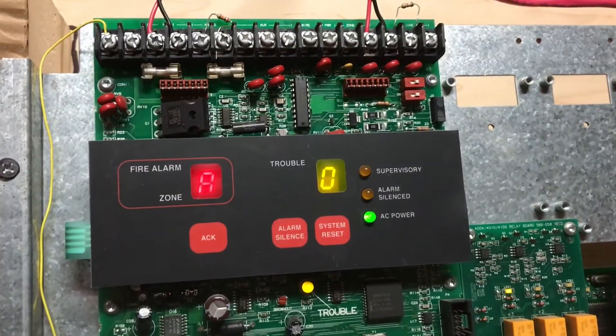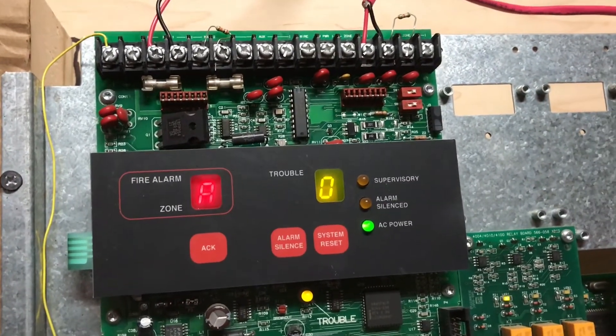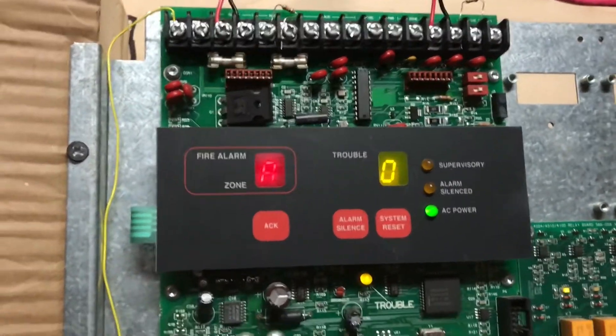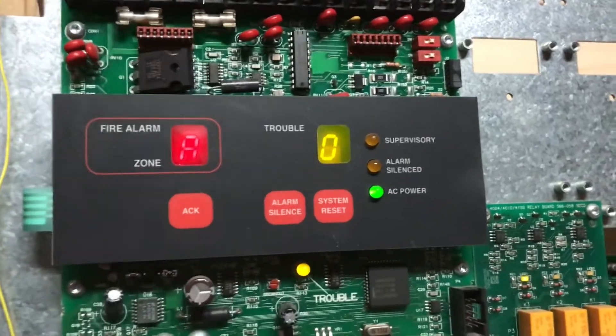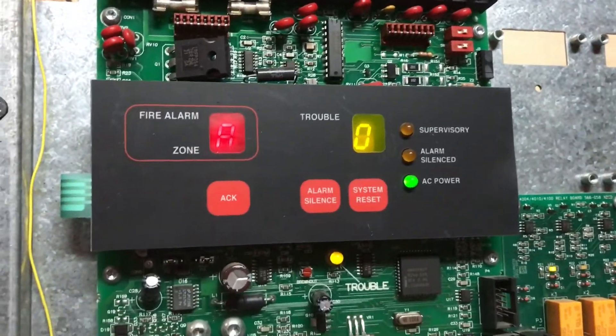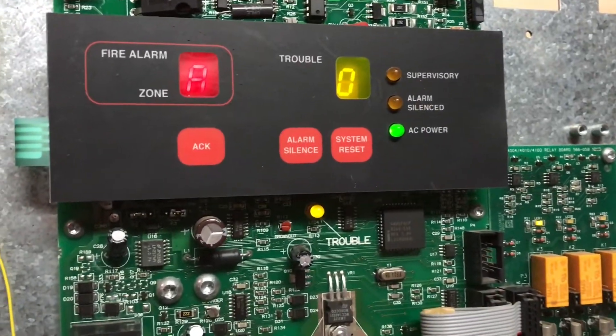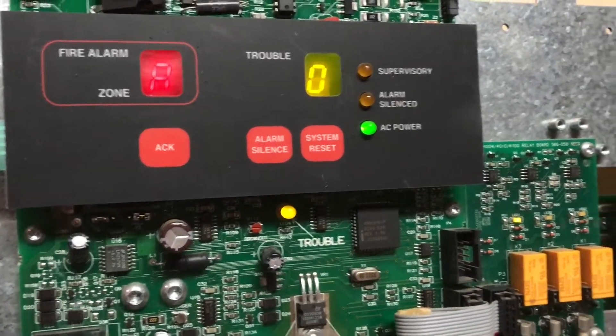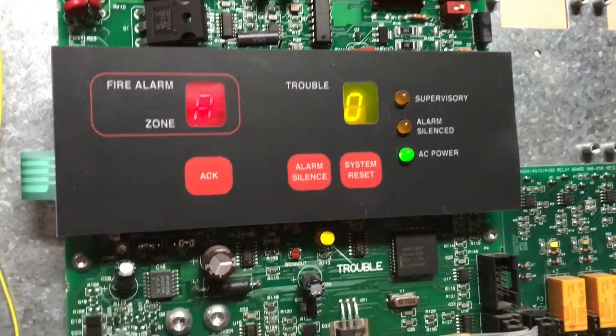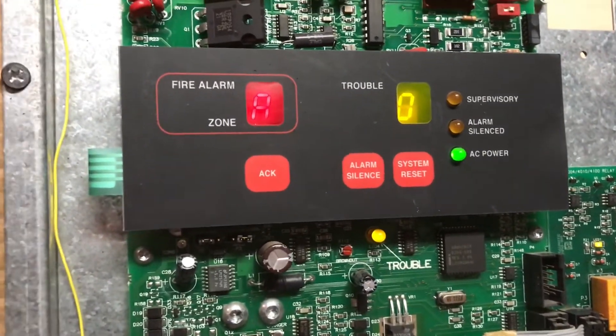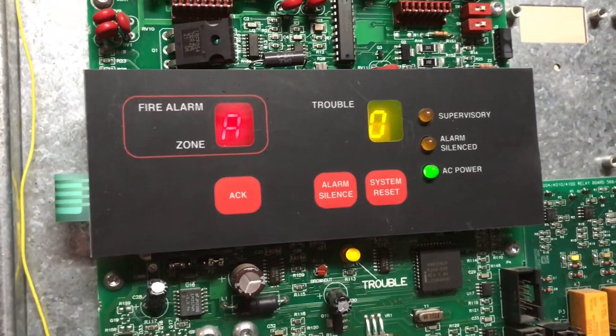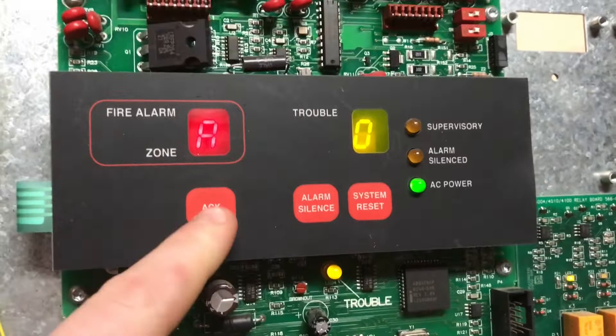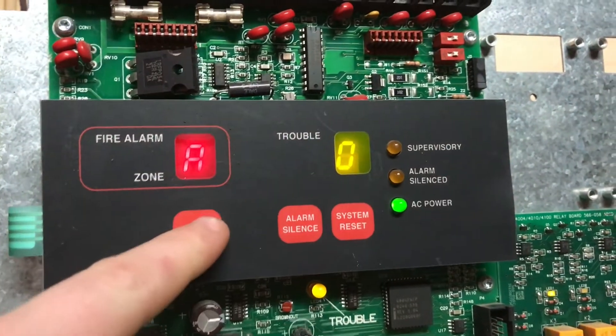A is for signal silence inhibit. What that does is it gives a certain amount of time before the panel can be silenced. If you want it for one minute, that means after an alarm has been activated, you have to wait at least a minute before you can silence the system. But I don't need any of that.